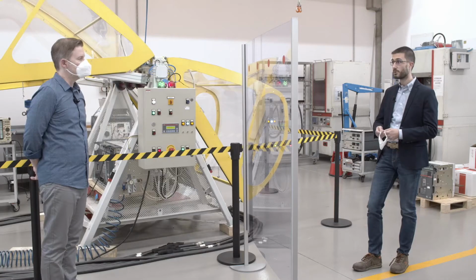But then, working on the thermal part, because for the PV maybe they are not so critical from the short circuit point of view, but they are for sure critical for the thermal matters. Once we dealt with the 50 degrees calibrations, we found some matter a bit strange, and we suggested to UL to adjust a bit, and in the following edition we found that.